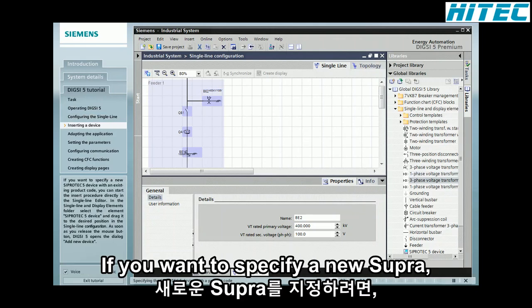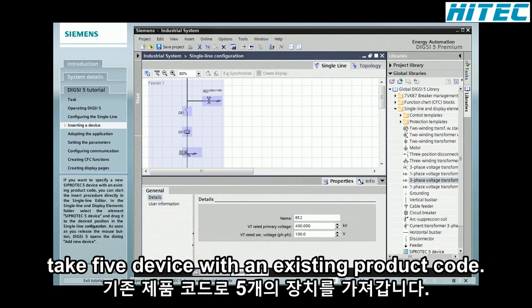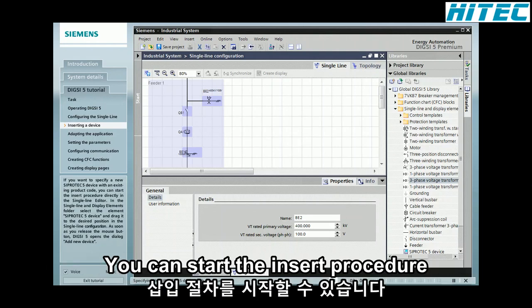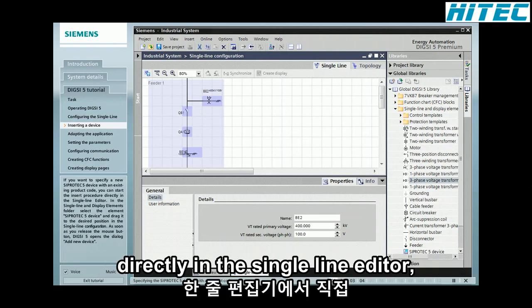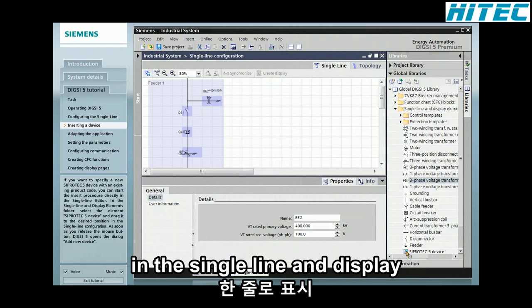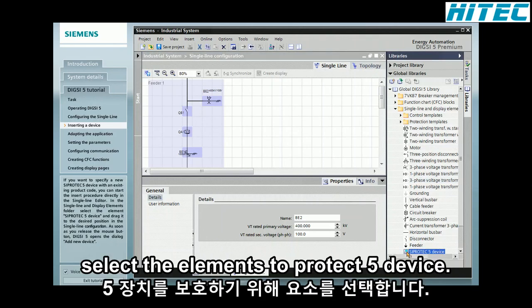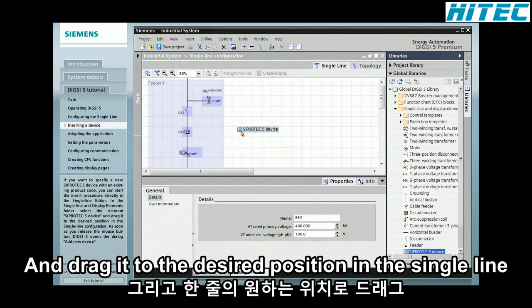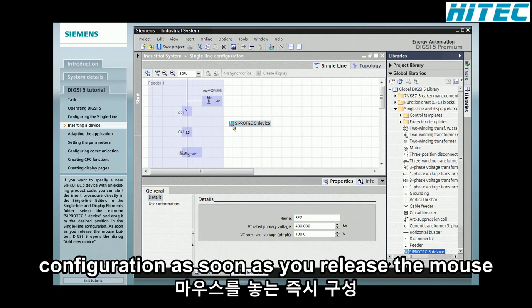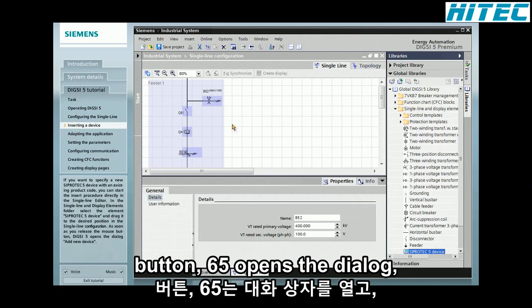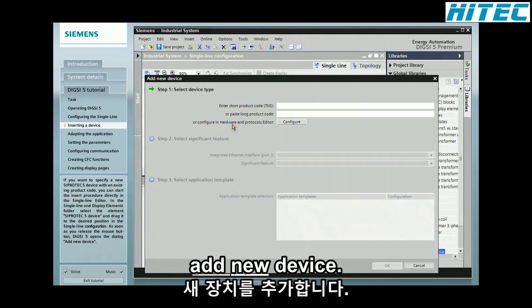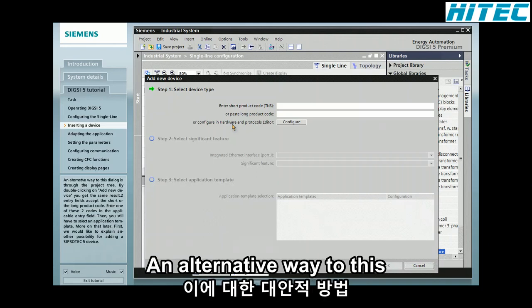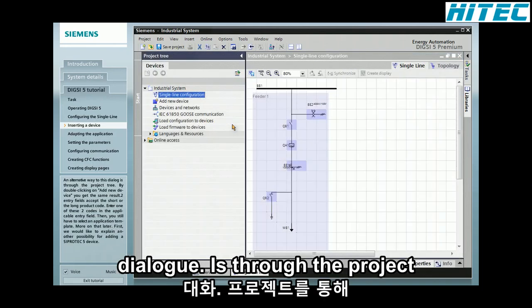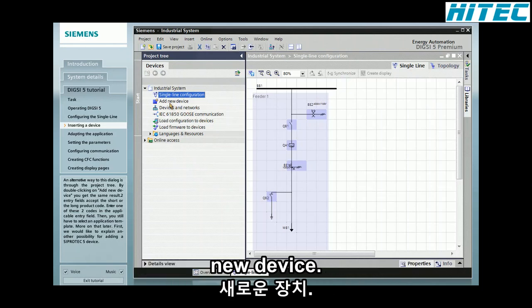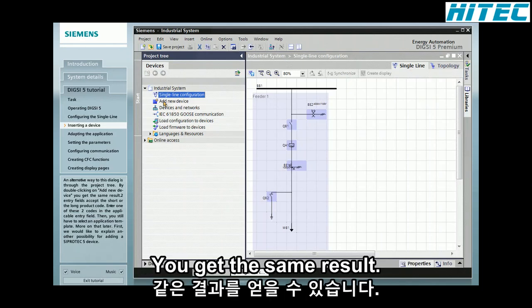If you want to specify a new SIPROTEC 5 device with an existing product code, you can start the insert procedure directly in the Single Line editor. In the Single Line and Display Elements folder, select the element SIPROTEC 5 device and drag it to the desired position in the Single Line configuration. As soon as you release the mouse button, DIGSI 5 opens the dialog Add New Device. An alternative way to this dialog is through the project tree. By double-clicking on Add New Device, you get the same result.